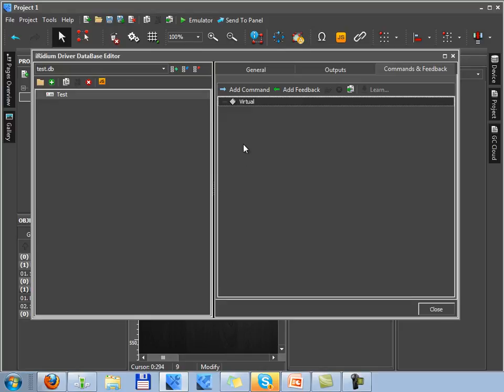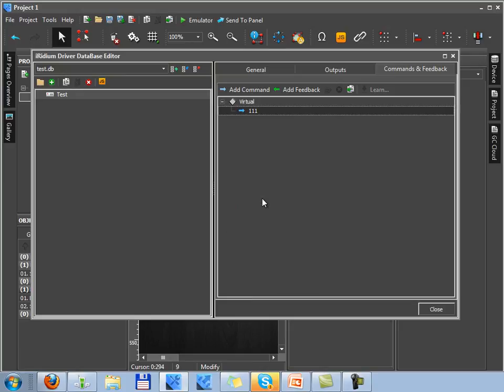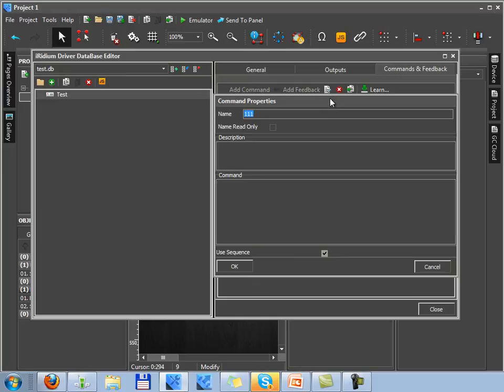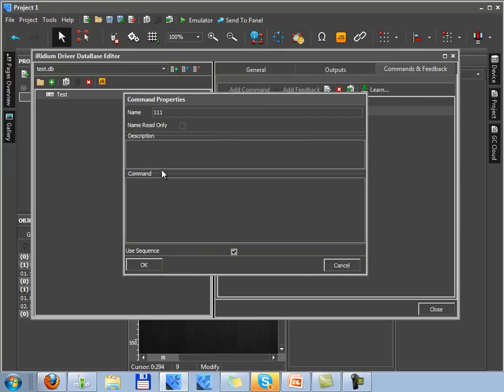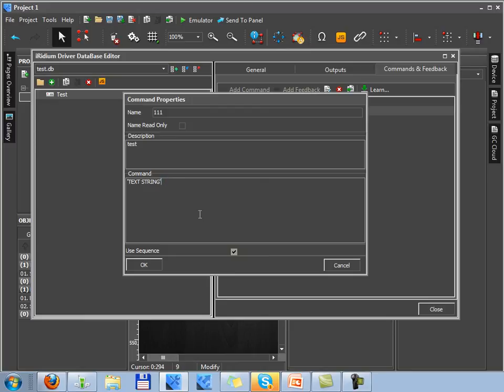And the third tab includes commands which must be sent via COM port of the device. So you should add a new command, write its name and by double-click the command properties window will open. And here you can edit this command. In the command body you can indicate its description. And you can also form a string of the ASCII or HEX formats. Here you can input any data. But don't forget about Iridium syntax. Don't forget about using of single quotes for the string of the ASCII format and separators as commas for data of the HEX format.